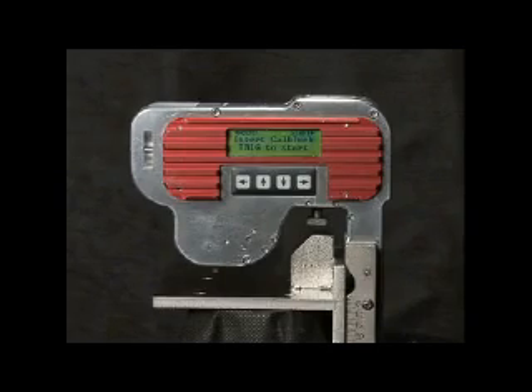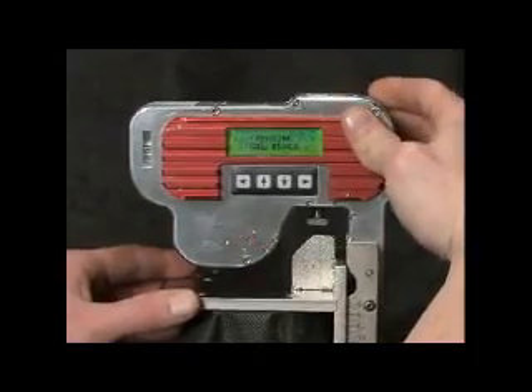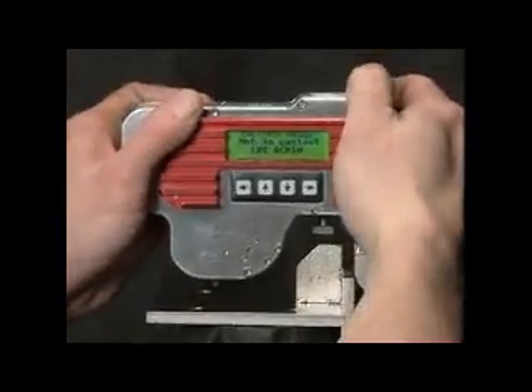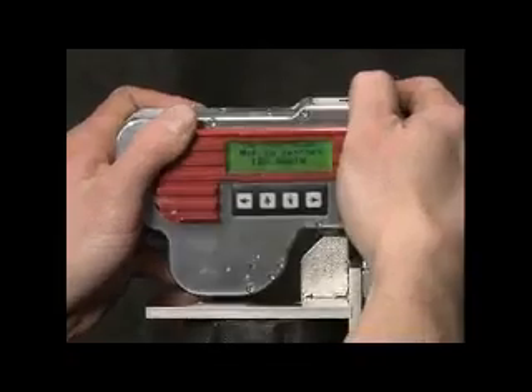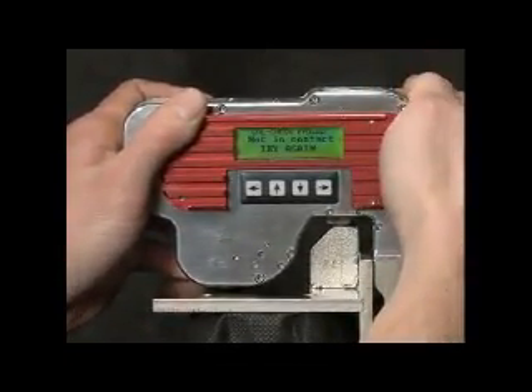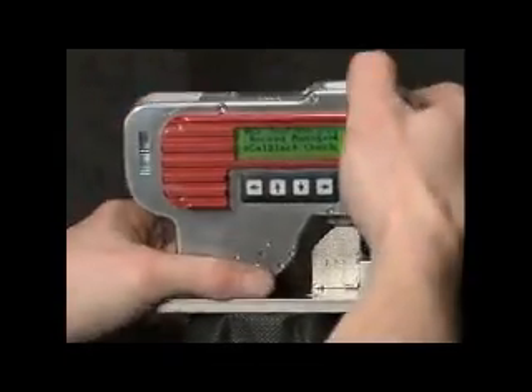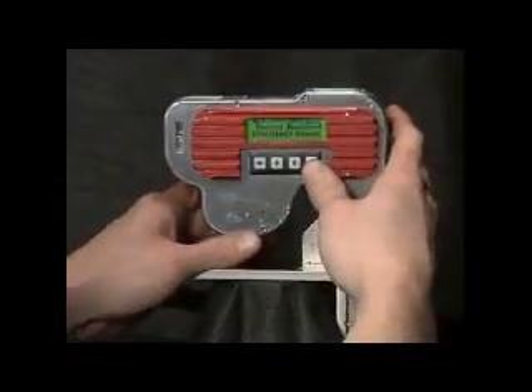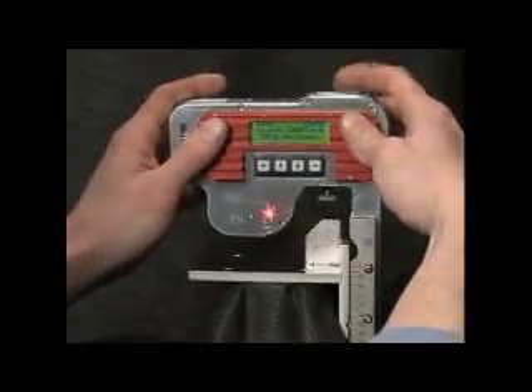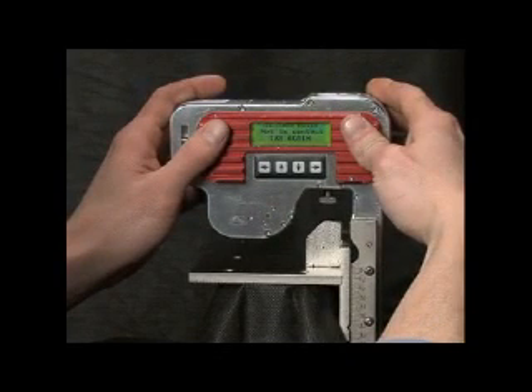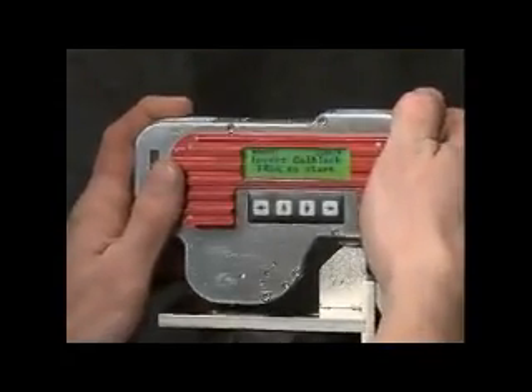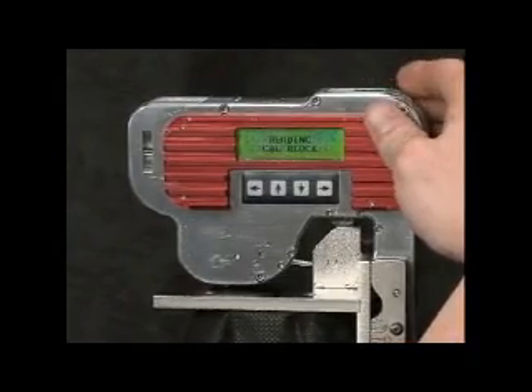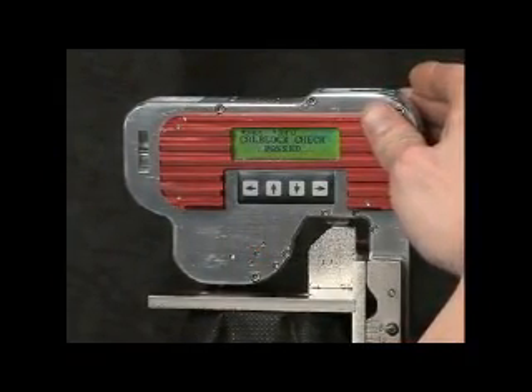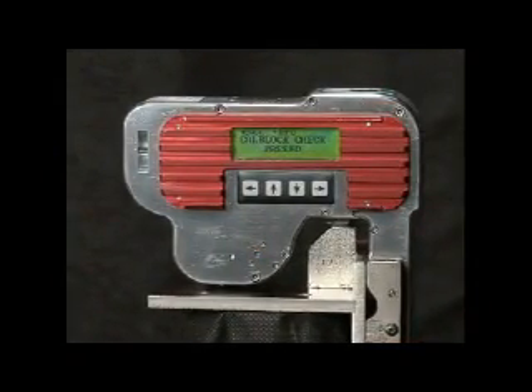When placing the CalBlock onto the gauge, make sure that the flange height plunger is centered on the CalBlock. Then verify that the CalBlock is firmly engaged. This may take some practice to get used to the correct placement. When you have the CalBlock attached, press the trigger. If the CalBlock is incorrectly engaged, you will get a message that calibration failed because the CalBlock is not in contact. Realign the CalBlock and try again. When properly aligned, the gauge will indicate whether it passed or failed the calibration check.